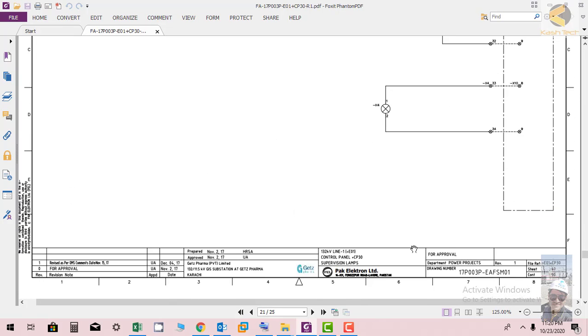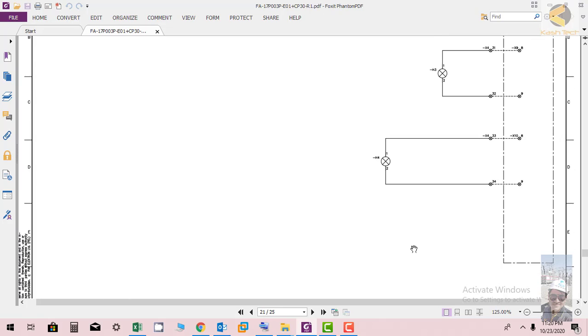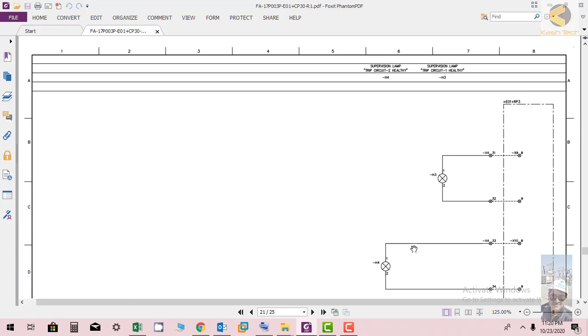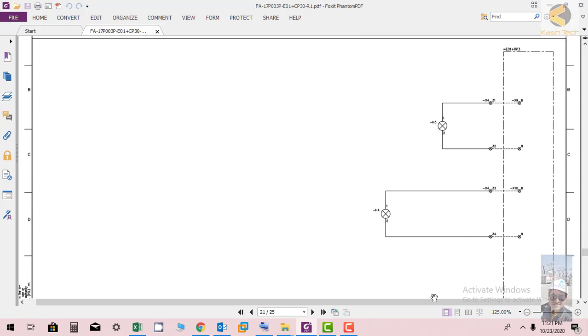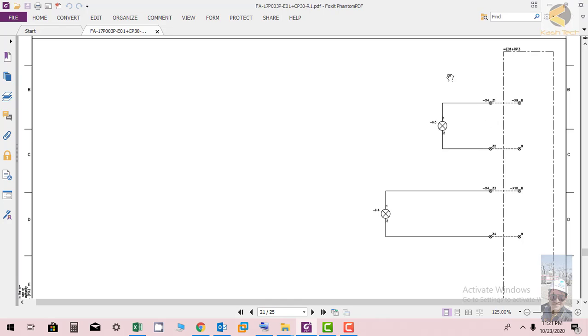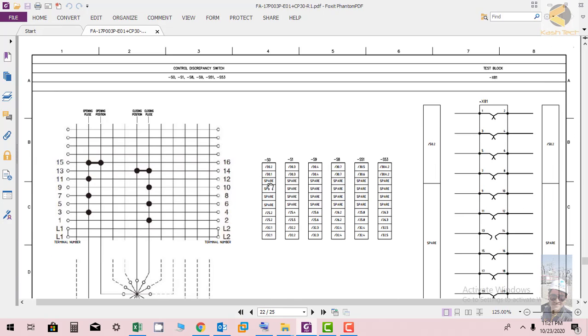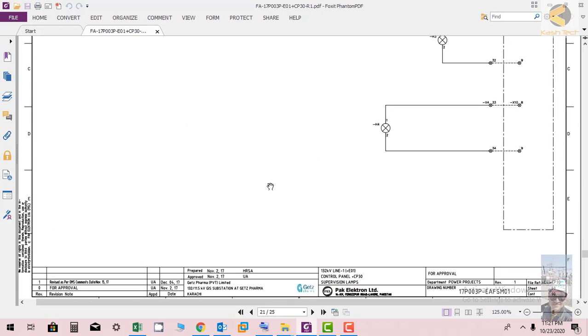The next sheet is basically control panel supervision lamps. One lamp is showing trip circuit one healthy and another lamp is showing trip circuit two healthy. It is coming from the protection panel E01 plus RP3. If you'd like to understand more about this interface drawing, I have a separate lecture on the protection panel where you can find detail how it works.